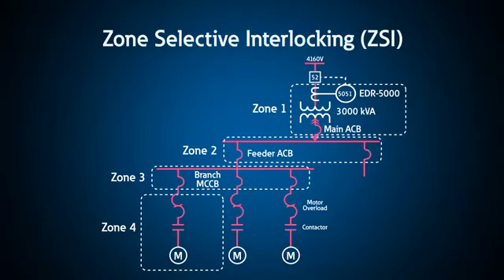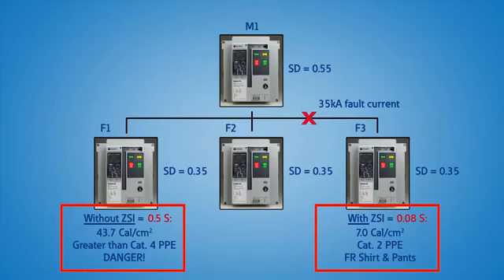Through high-speed communication, zone selective interlocking, or ZSI, deactivates the preset delays or coordination settings on the circuit breaker closest to the fault, which then trips with no intentional delay. This reduces the amount of time current flows and the amount of arc flash energy and stress the system encounters during fault conditions.